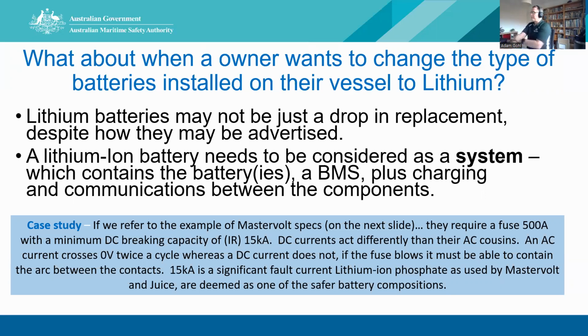So the Mastervolt on the next slide, they require a 500 amp fuse with a minimum DC breaking capacity of 15,000 amps, so kilo amps. So the potential energy in these batteries is a lot higher. And the issue with the DC current, you can open the terminals, and as you open it, the spark just grows. It ionizes the air, and it reaches a point where the plates are far enough apart that it will break. Whereas an AC circuit has a sine wave, so twice a cycle, it switches off, so the switch isn't exposed to that much current, unlike a DC. That's why DC terminals and contacts are much larger.